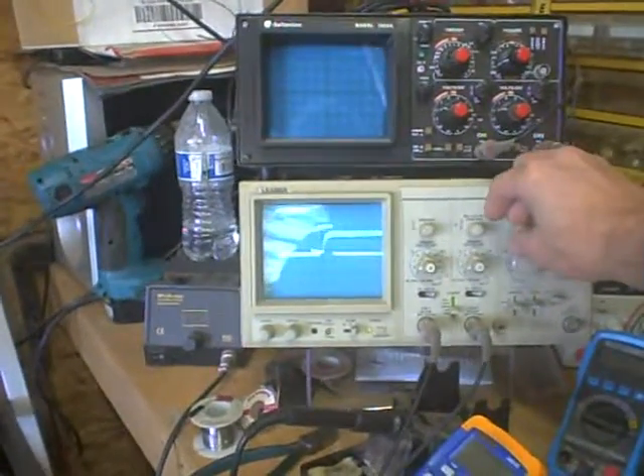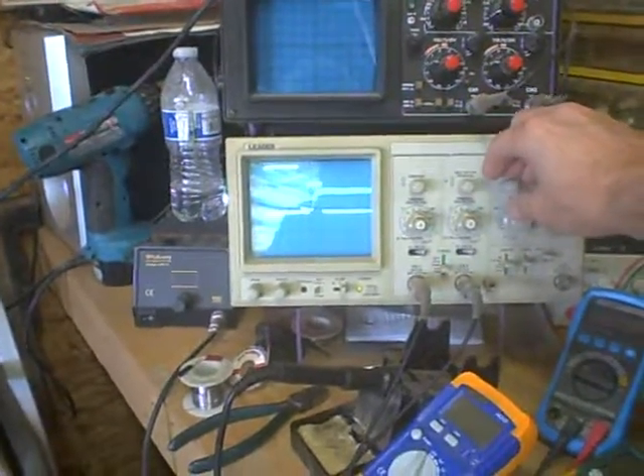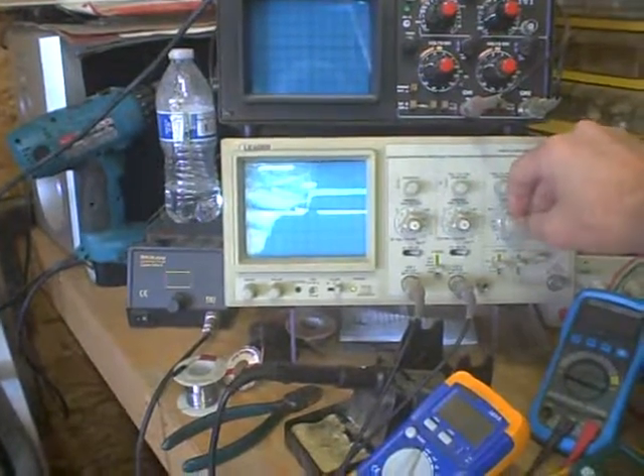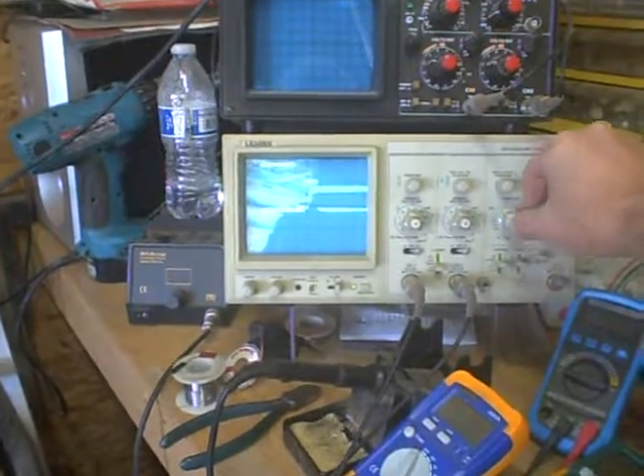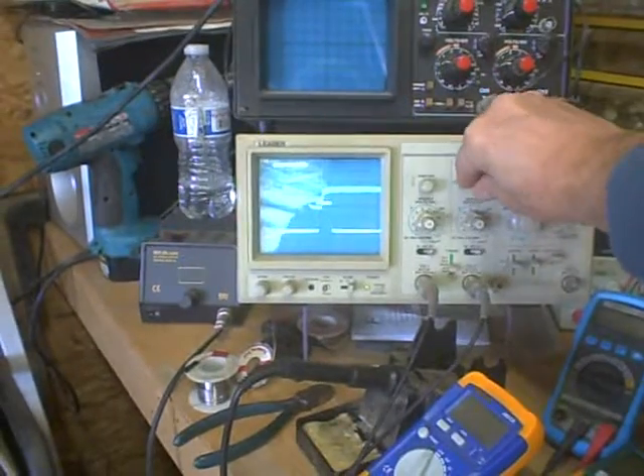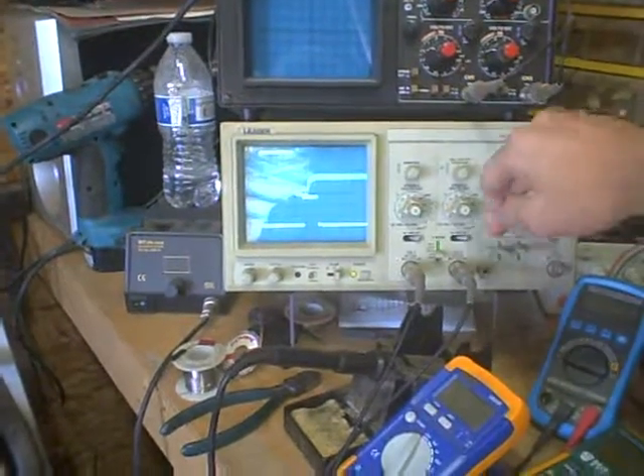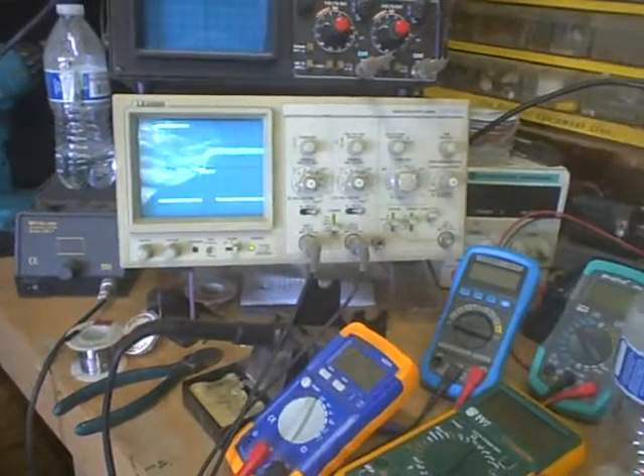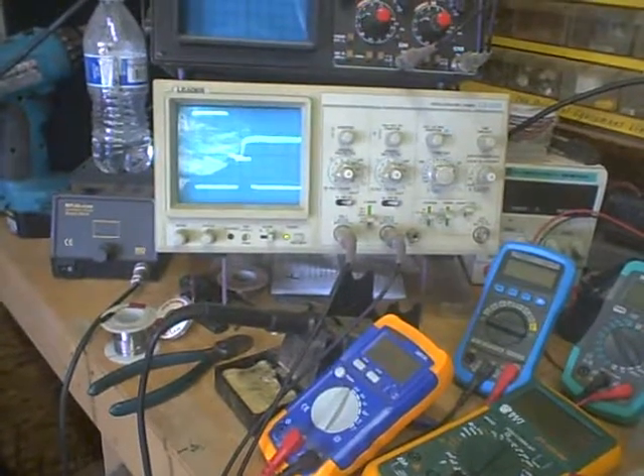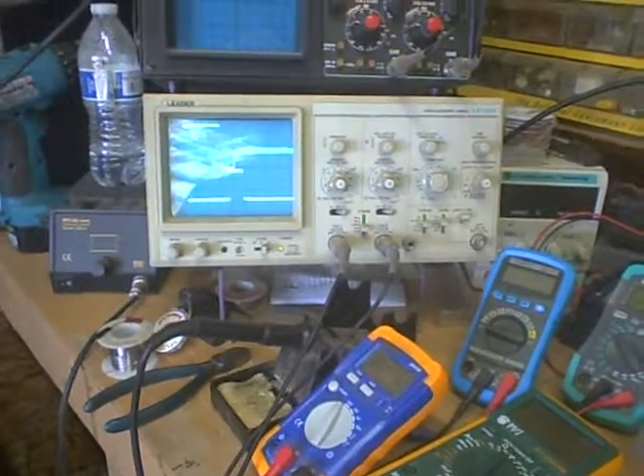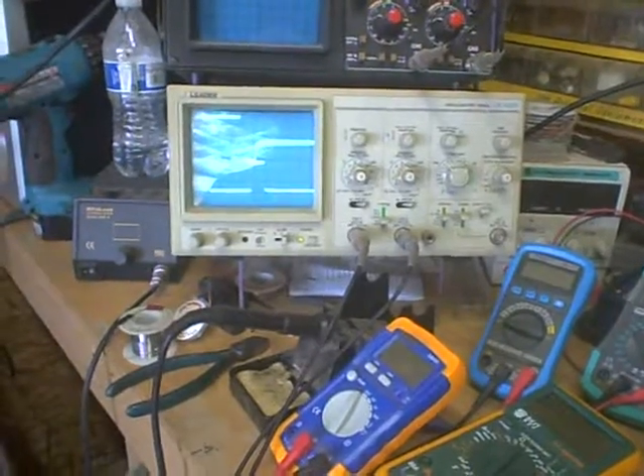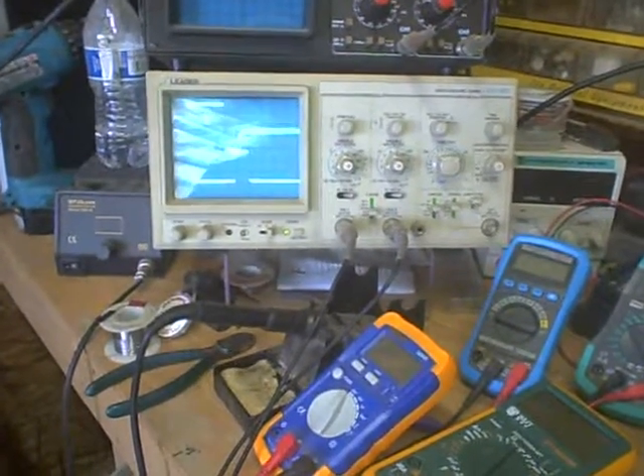Right now we're set so it's a 30 microsecond transmit pulse. It's a 12 microsecond wide sample pulse. And right now I've got it set at 8 microseconds. It'll actually go down to 6. I can actually adjust it using the onboard trimmer down to 3 microseconds before it drops out.